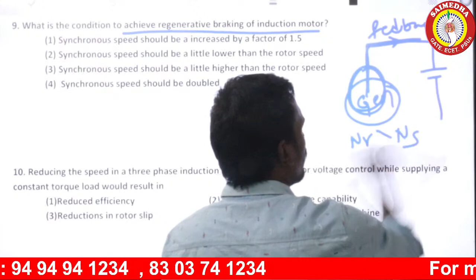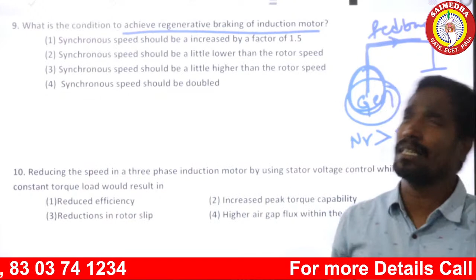When is it possible? When the machine acts as a generator. When the rotor speed is greater than synchronous speed, then the motor acts as a generator and it will give supply in reverse, fed back to the supply.